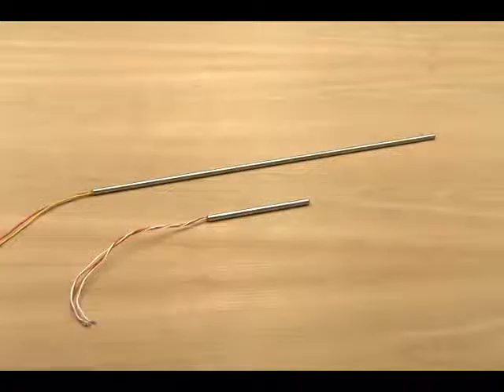One of the routine maintenance functions in a process plant is replacing temperature sensors from time to time. The sensors themselves are usually very durable, but sooner or later you're going to have to pull the element out of a thermowell and put in a new one. Here's a typical sensor element.